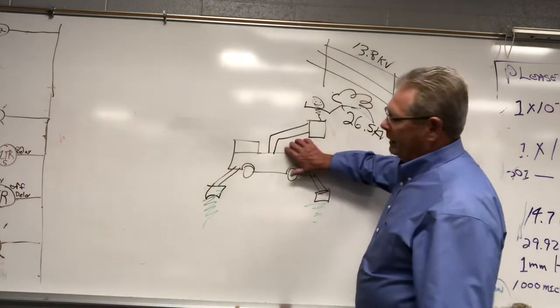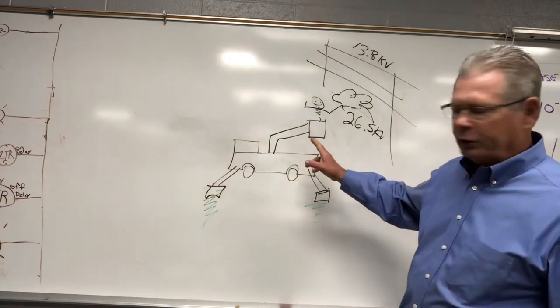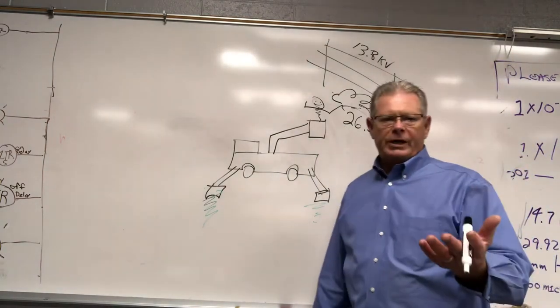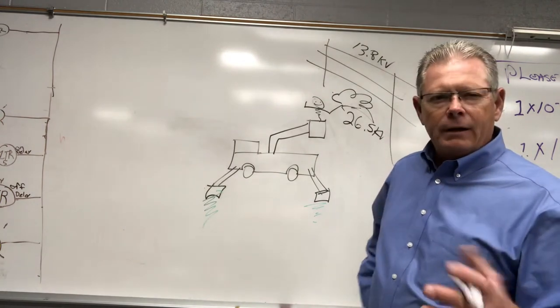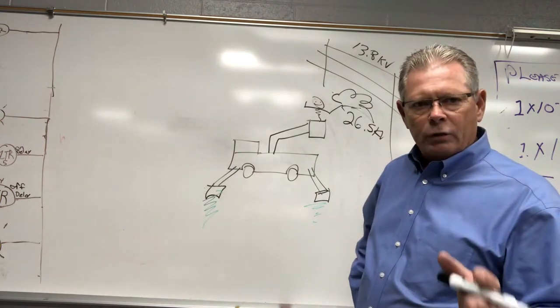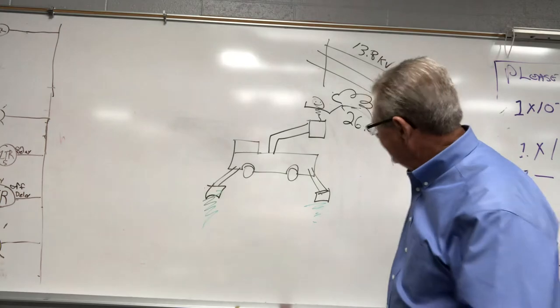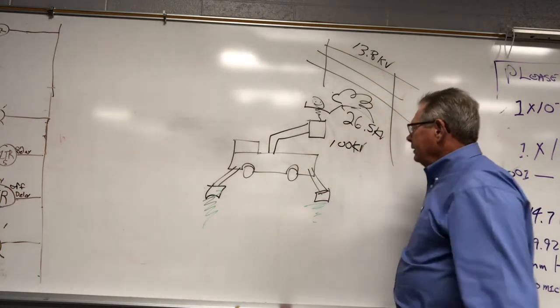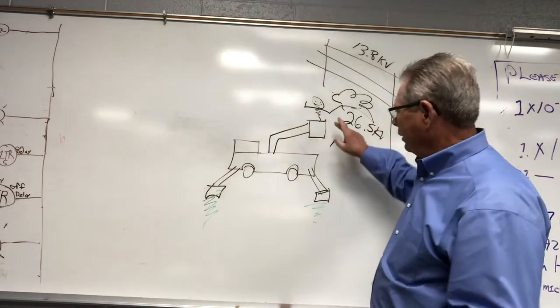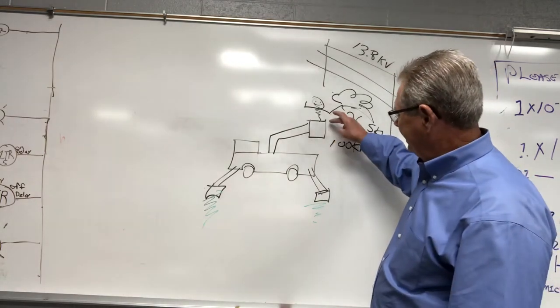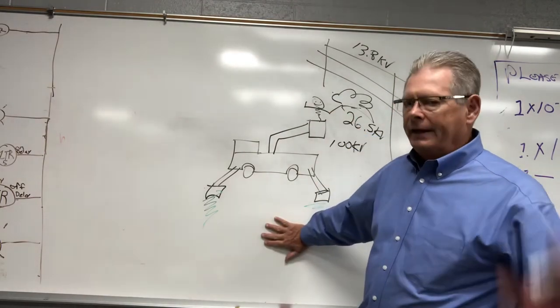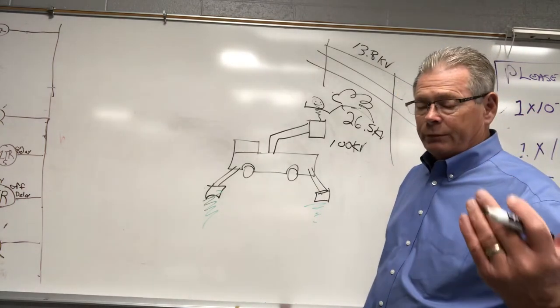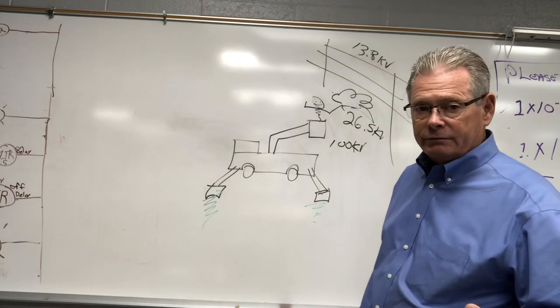Now the bucket truck, they have fiberglass booms, they have fiberglass buckets. And once a year they have to be tested to see if they can withstand the voltage they're built for. It's not uncommon to have a 100 kV bucket truck. So that means they're going to test this bucket truck to see from here to ground if it can withstand, if the insulation value can withstand 100,000 volts every year.